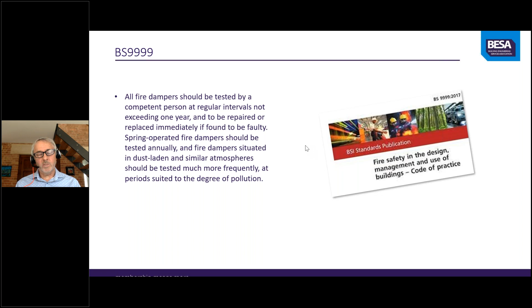So installation. To enable the fire damper to be tested and reset, access panels need to be installed. Access panels need to be quick release, insulated, sealed panels, all manufactured and installed to the BESA specification DW144, which is the sheet metal ductwork specification. The required location of these is shown in that specification, and they're also shown in TR19 Grease Table 3, which is also a BESA publication, and it also tells you who's responsible for positioning the panel. So TR19 is fire risk management of grease accumulation within kitchen extract ducts.